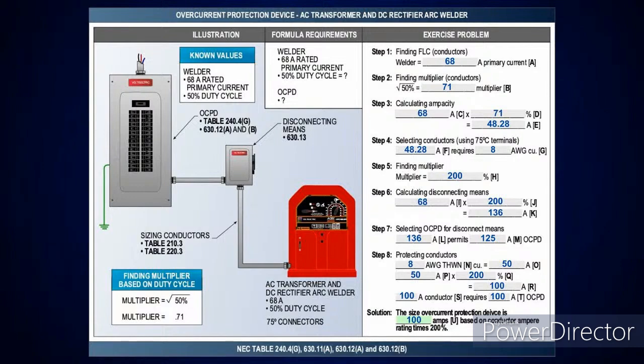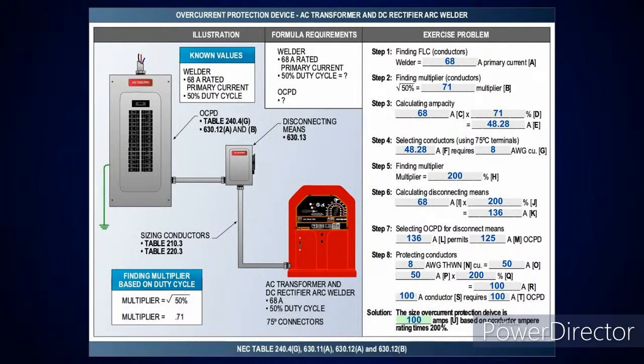And I said, when you're dealing with non-motor generator and motor generator welders, you want to look at Table 630.11(A), and you're going to get that duty cycle. Then there'll be two columns, one for the non-motor and one for the motor, and you get your multiplier from there. Then we check the conductor and everything at 200%, because when you look at 630.12(A), it tells you the overcurrent protection device is rated or set at not more than 200%. So that means I would drop down, doesn't it?